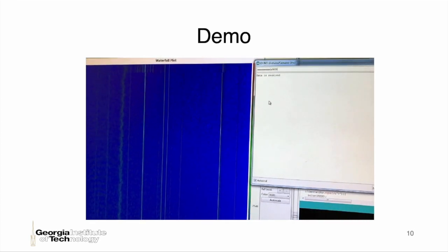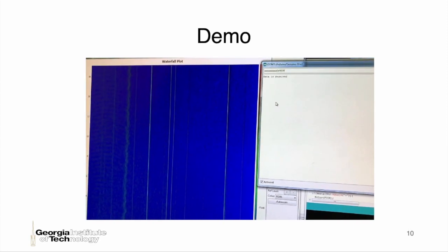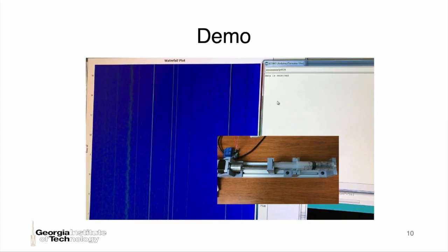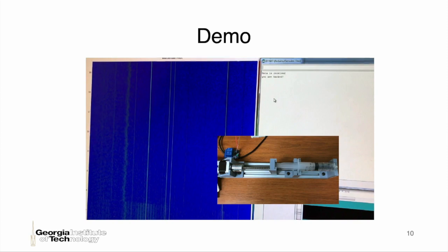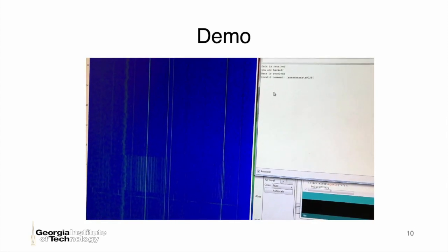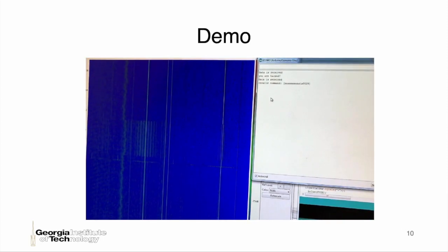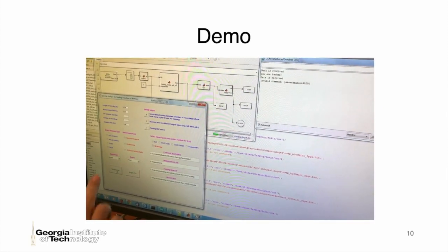Now let's start the attack by doing the buffer overflow. We are sending a command followed by the return address of the function that moves the syringe. As you can see, once the command has been sent, the syringe immediately starts to move, and this time the signatures look different from what they were before in the actual execution, which is how we detect it.